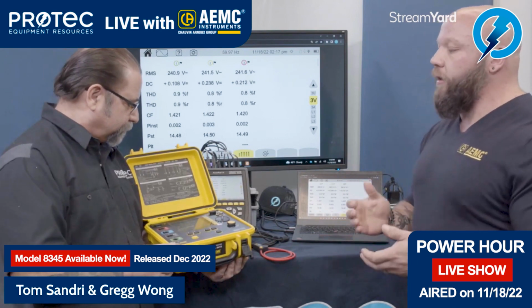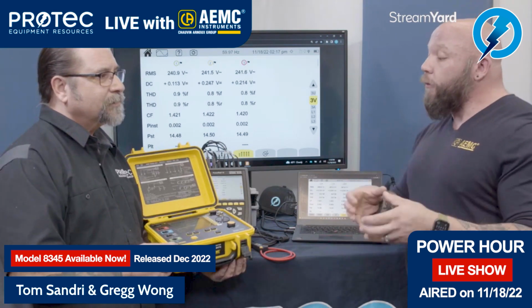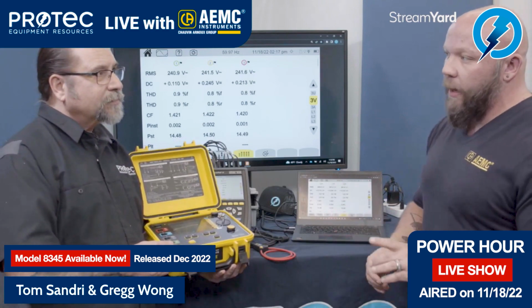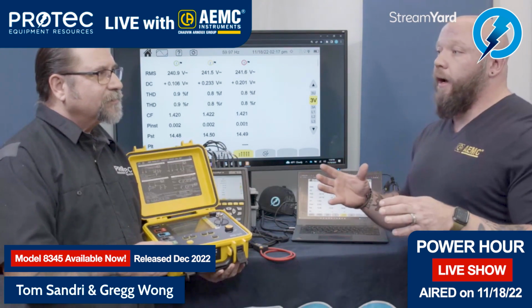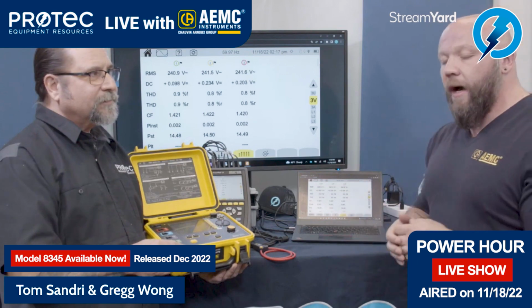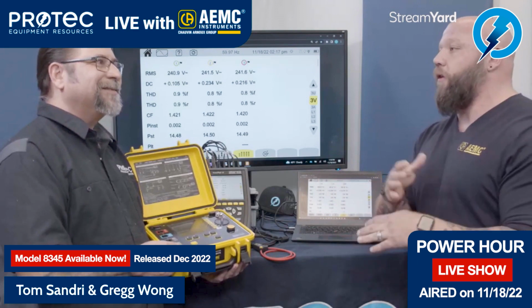So for our utility customers out there or contractors that are working on the footing or needing to understand the footing resistance of a transmission tower or also a communications tower. It's a little known fact that we can use this on just an individual communication tower as well as a transmission tower without disconnecting the static overhead, without setting a bucket truck with a whole crew and the cost of it.